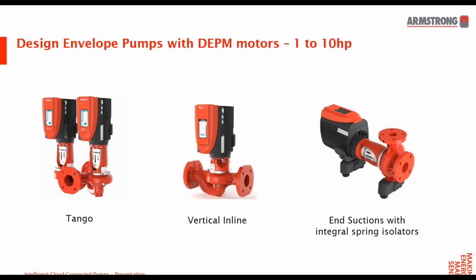Hey, Dave, I have a question about if you're trying to use one of these design envelope pumps with a BMS, do you need a separate control panel, or is there an overriding control panel for all of these systems? Actually, no, you don't require an extra control panel. These pumps are all equipped with BMS protocols. They work off Modbus and BACnet, both BACnet MSTP as well as BACnet TCP/IP, so you can do internet connections as well. It includes a list of BACnet points and Modbus points, so it can communicate directly with the building's BMS, and you don't need an external control panel on top of that.